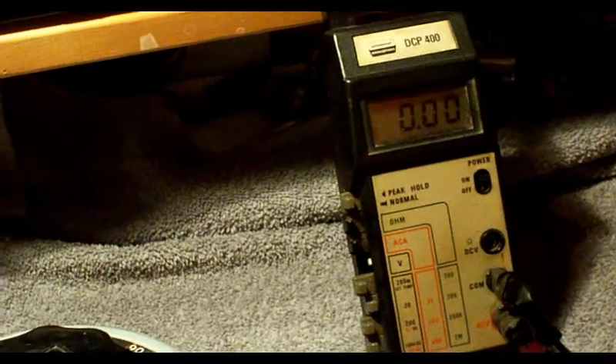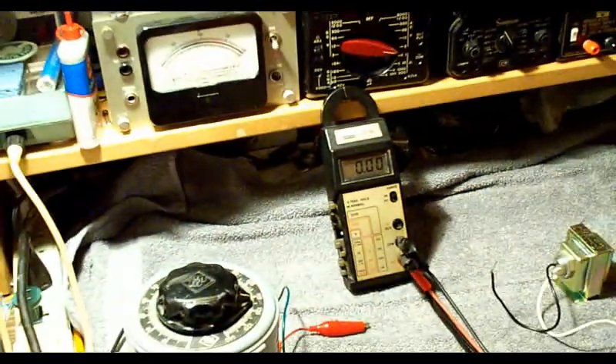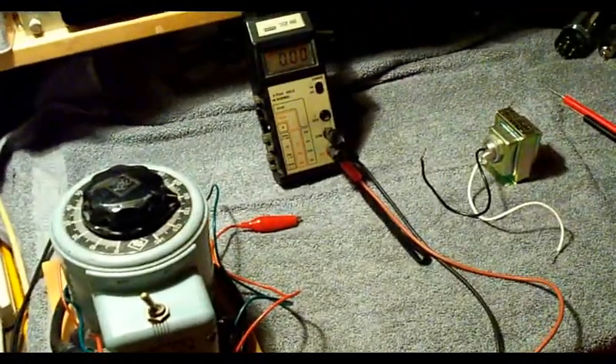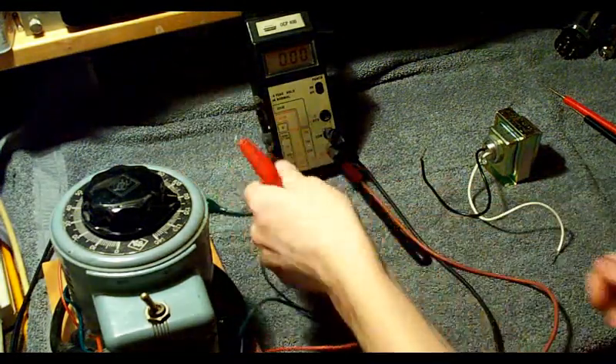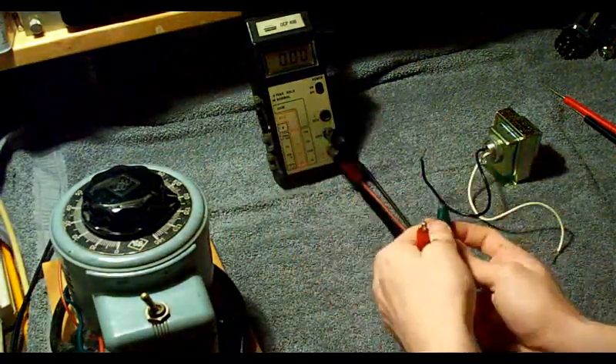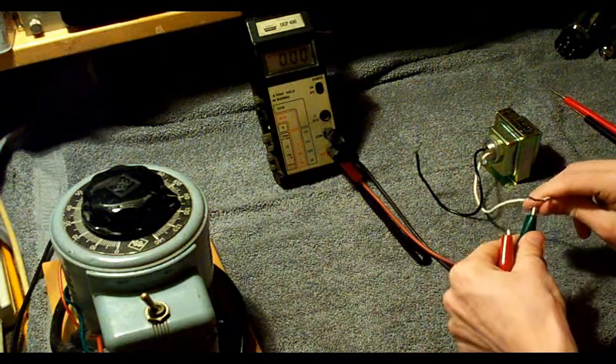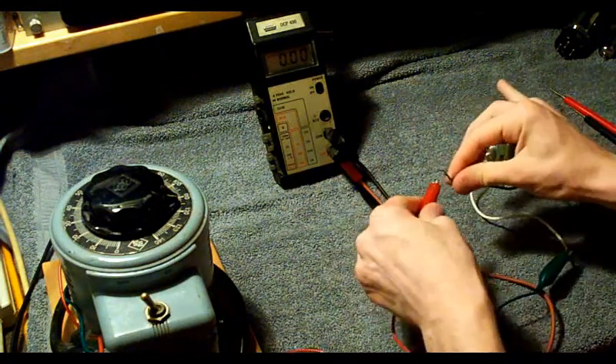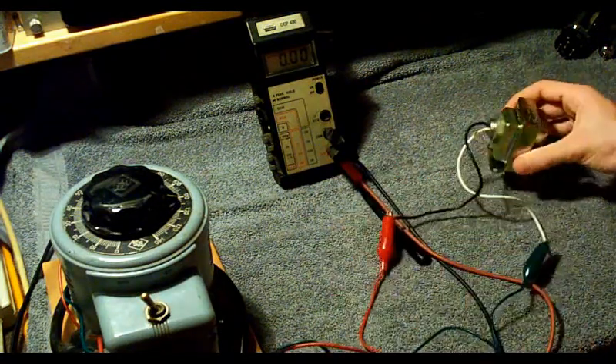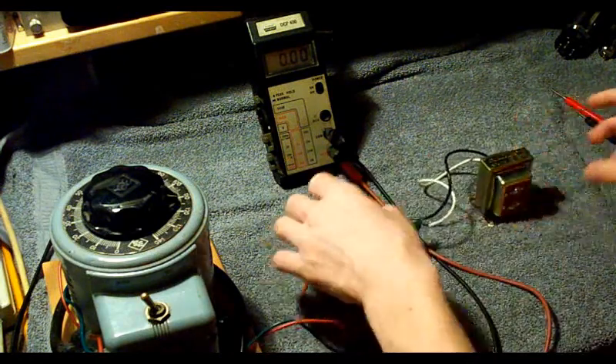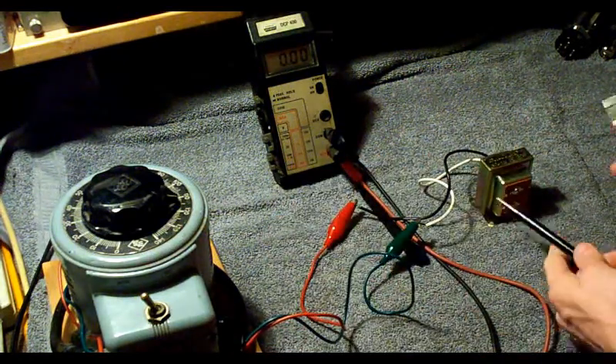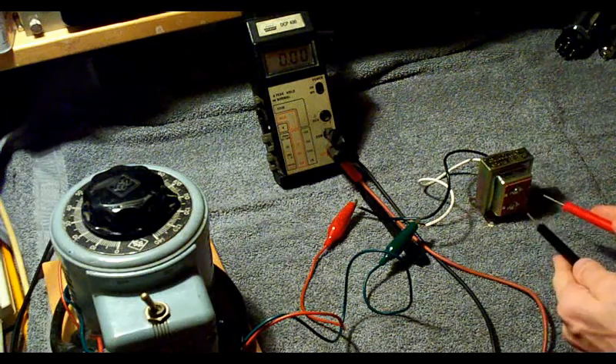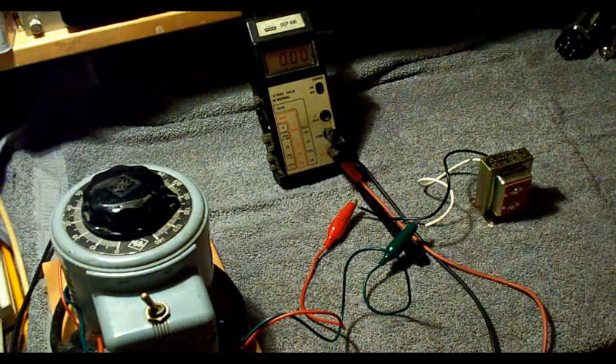And I'll zoom out here so I can show you how I'm setting this up. So if we look right here, these clip leads are going to be at 120 volts potential, and I'm simply going to connect them across the primary winding of the transformer, just like if it was hooked up to the wall. Make sure these don't short out. And we're going to put our meter across the output here, and we're going to read the secondary voltage, which should be around 15 volts or so, depending on what the primary is. So let's get a look at that meter.